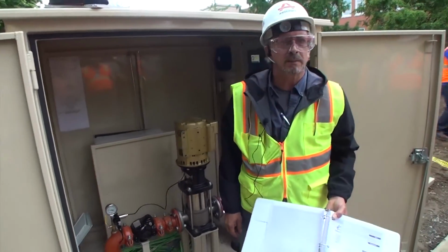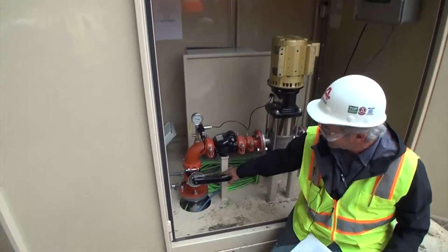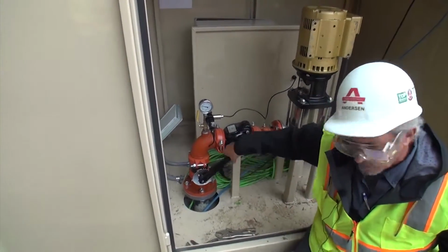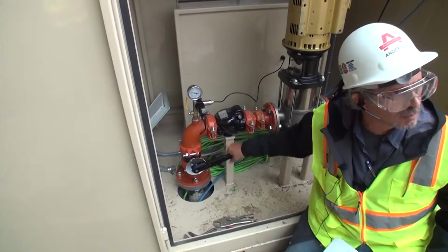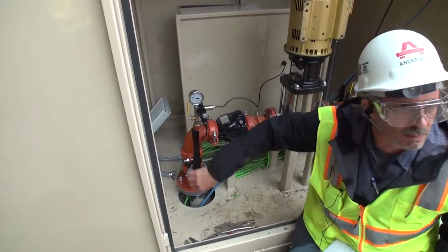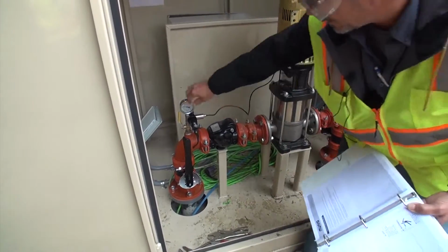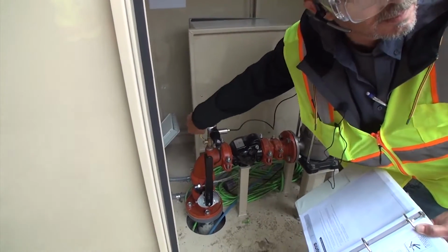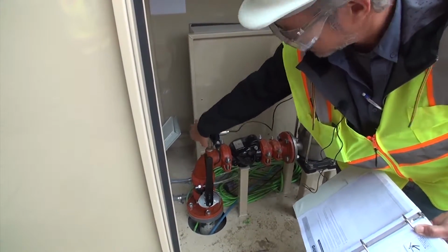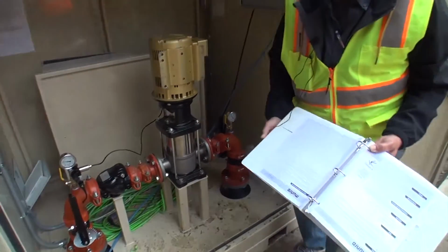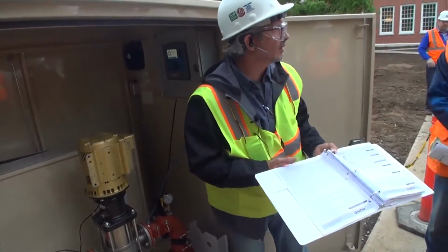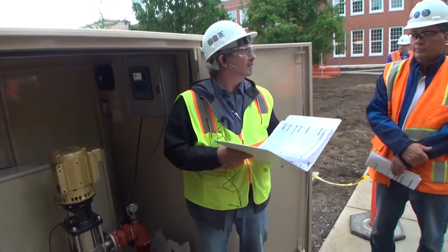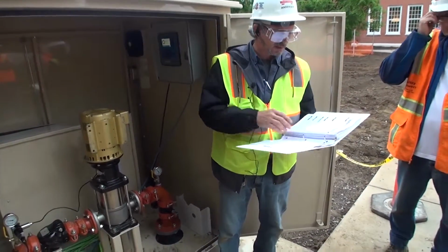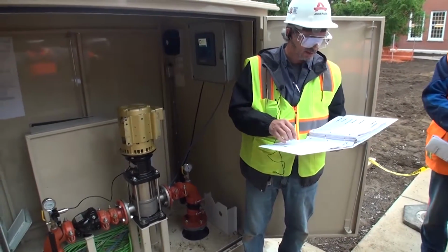When we talked about the maintenance on this thing and you want to wipe it, we're talking about this where it seals to close. That's what you're trying to wipe, and then put it back to open. We recommend you do all of the valves. Just work them back and forth a couple of times. It's kind of like the valves underneath your sink. It's really horrible when you have to replace that valve and it doesn't work anymore because you haven't exercised it.